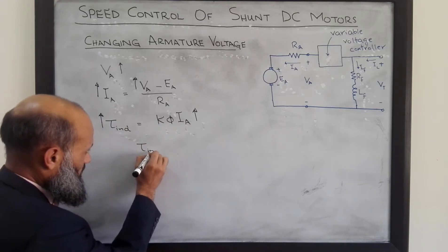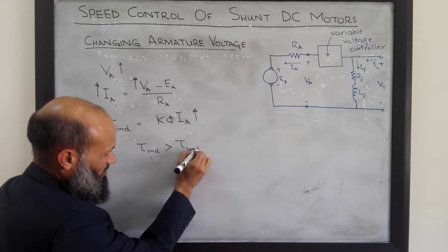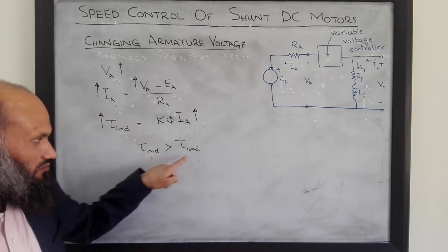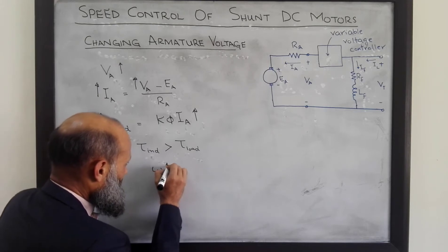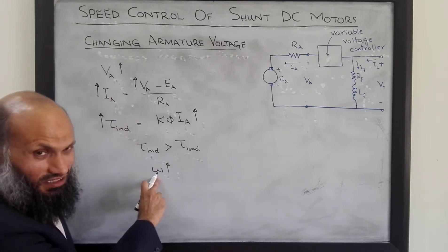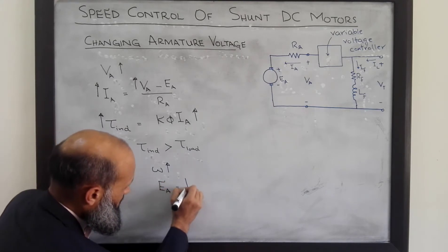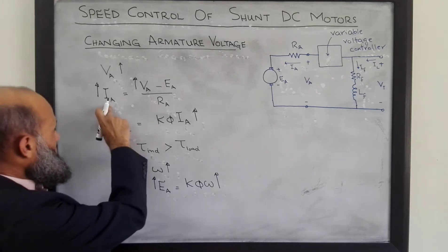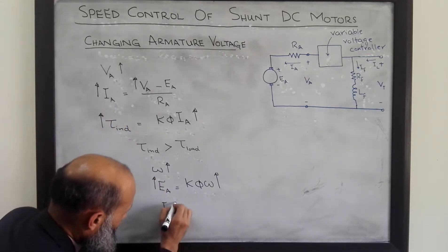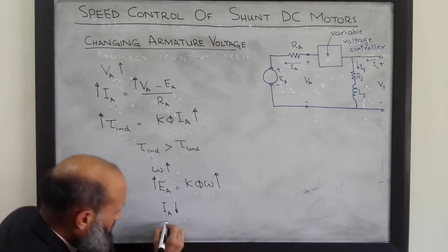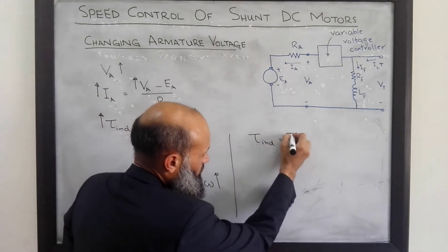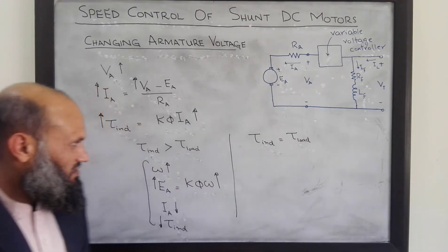As induced torque becomes larger than the load torque — the torque applied by the mechanical load connected to the motor — the motor will gain speed. Due to the increase in speed, Ea = Kφ·ω will also increase, which in turn decreases the current, and the decrease in current leads to a decrease in induced torque. This transient effect continues until induced torque again equals load torque and the motor runs at a new steady-state velocity.